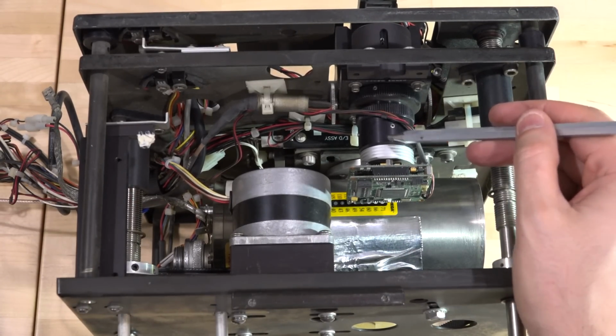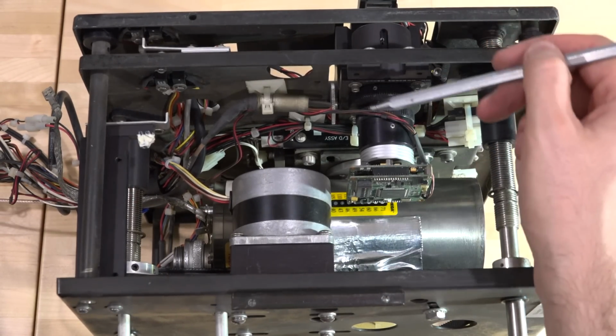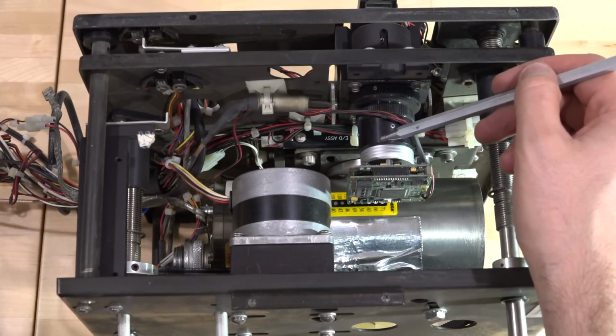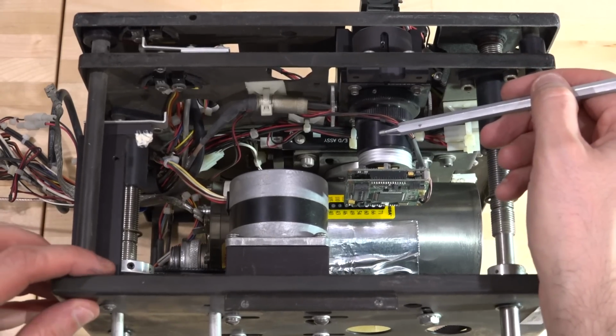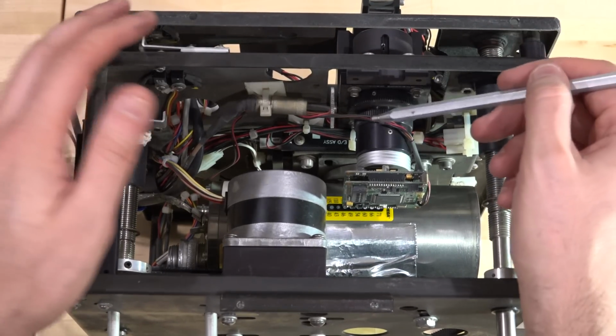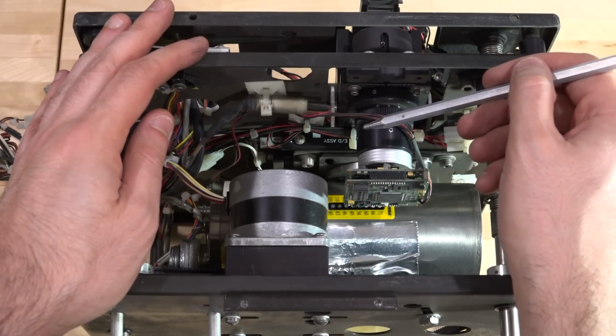And this is the camera. That camera connects to a bunch of mirrors and looks at a sample. We'll see the other side. But this is what was supposed to be faulty. Basically, no image was coming out. And without this camera, you don't know where the X-ray is pointed to. So it's going to be very difficult to use this instrument.